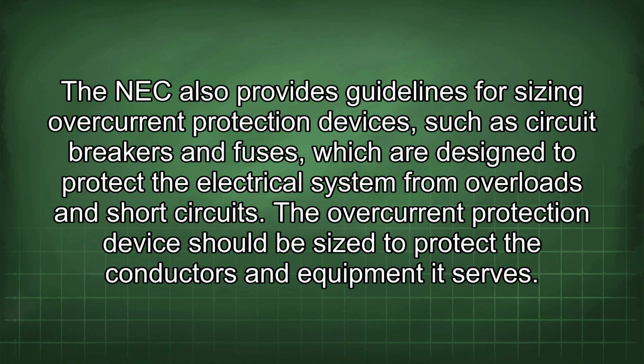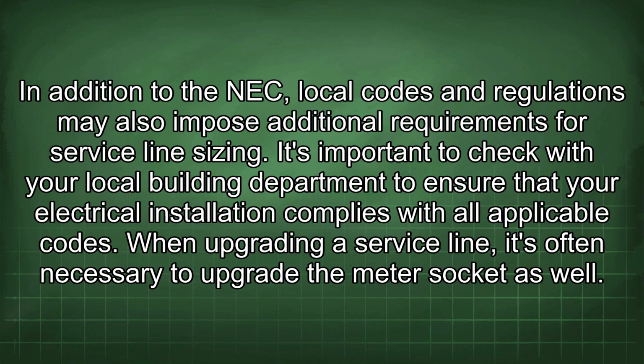The NEC also provides guidelines for sizing overcurrent protection devices, such as circuit breakers and fuses, which are designed to protect the electrical system from overloads and short circuits. The overcurrent protection device should be sized to protect the conductors and equipment it serves. In addition to the NEC, local codes and regulations may also impose additional requirements for service line sizing. It's important to check with your local building department to ensure that your electrical installation complies with all applicable codes.